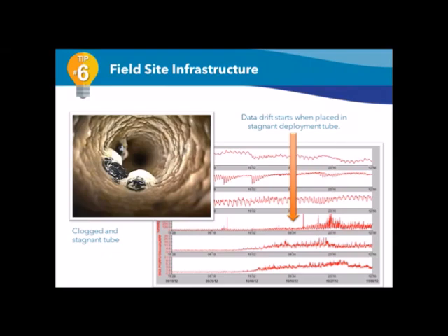So they removed the pipe and found that all the holes cut into it to allow water flow were covered with organisms. When the sonde was inserted, it created some water exchange at the bottom of the pipe, which caused the DO to go up initially. But as the sonde sat there, the water became stagnant and the DO began to drop. He was basically measuring the water quality of the microenvironment inside the pipe. Once the pipe was serviced and the sonde was put back into place, the problems with the DO disappeared.